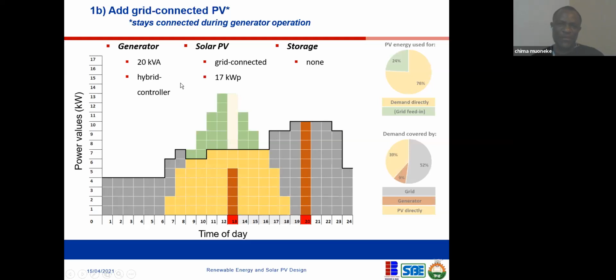Now this is another section. At this level you have the PV, but in this case if the grid fails your PV does not go out. There's what we call islanding in an inverter. If you have a grid connected PV system feeding into the grid, what happens when there's a grid failure? Maybe the utility decided to switch off the grid to do maintenance. That means your solar PV will keep feeding energy into the grid, which is dangerous. So there's what we call anti-islanding, a feature built into inverters. What it does is that anytime there's a grid failure, it automatically cuts your inverter from supplying power to the grid.